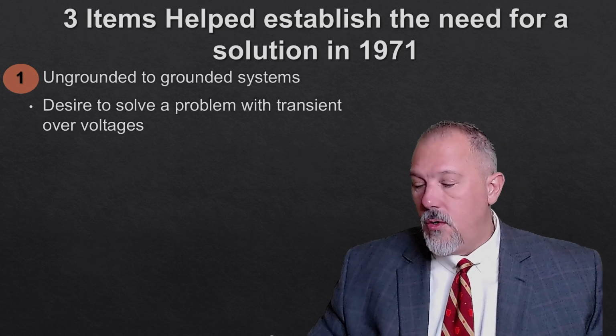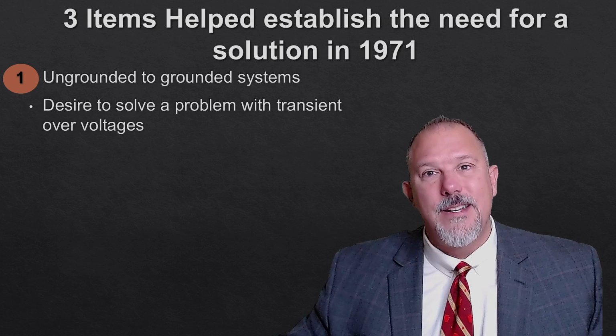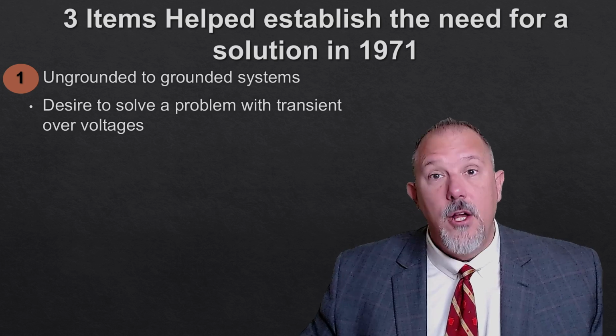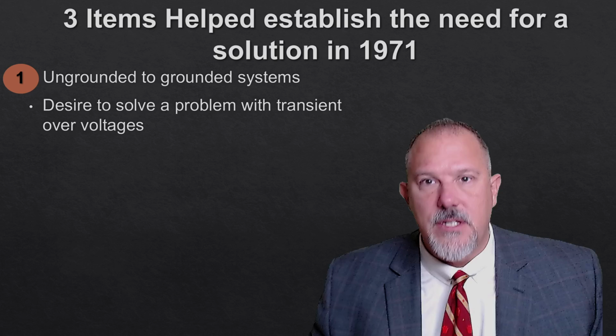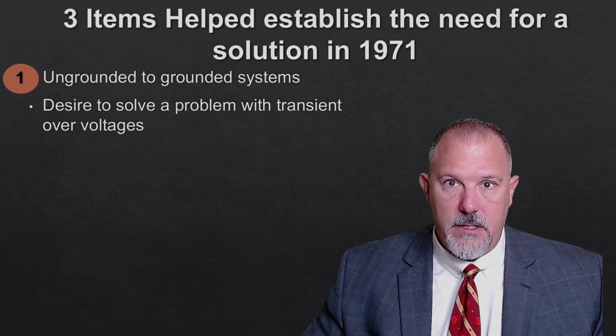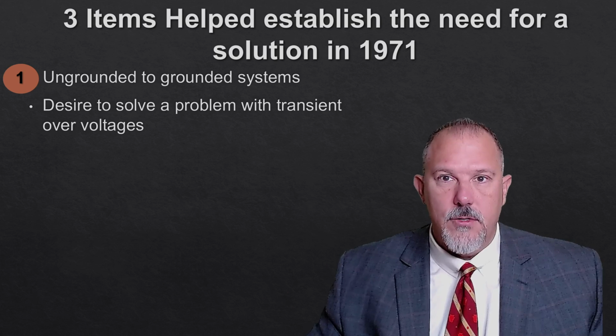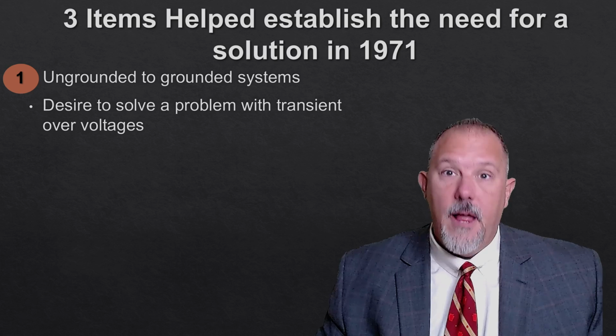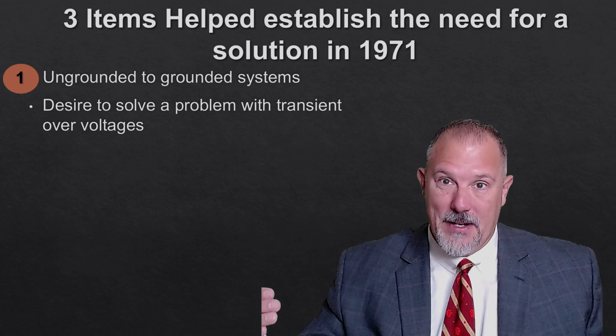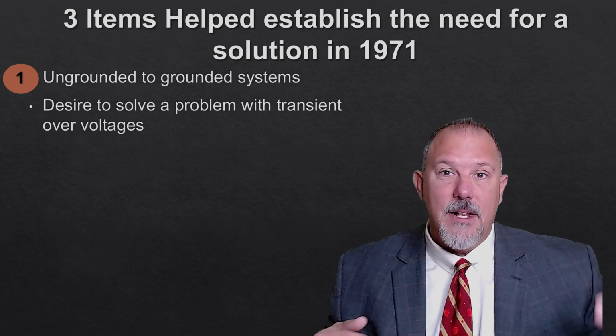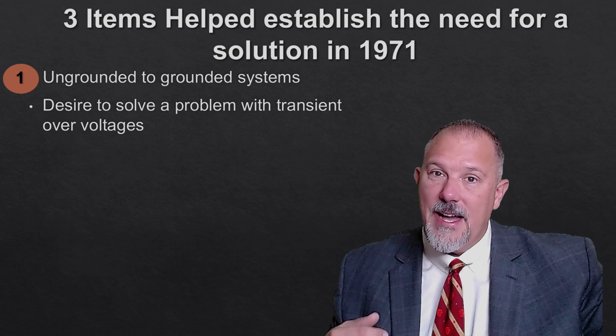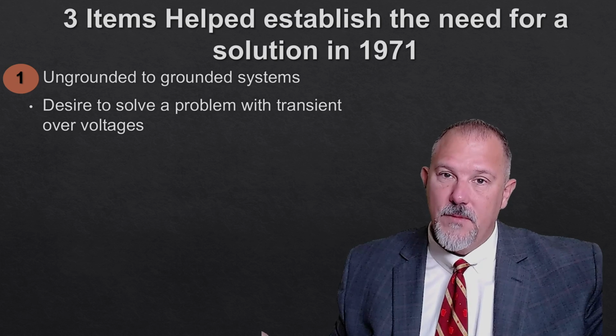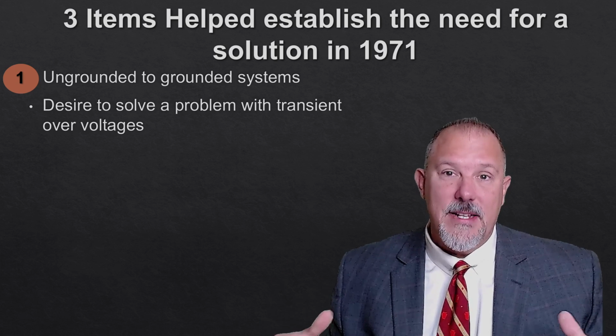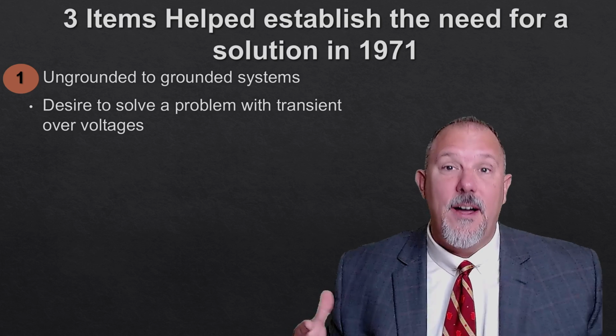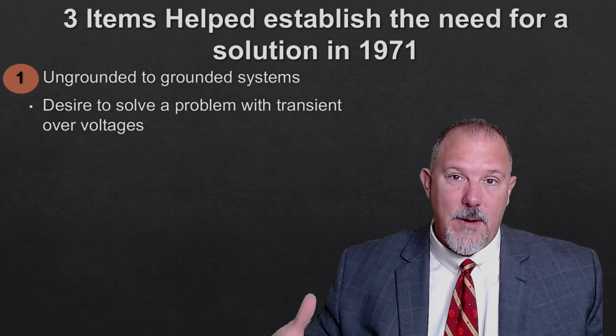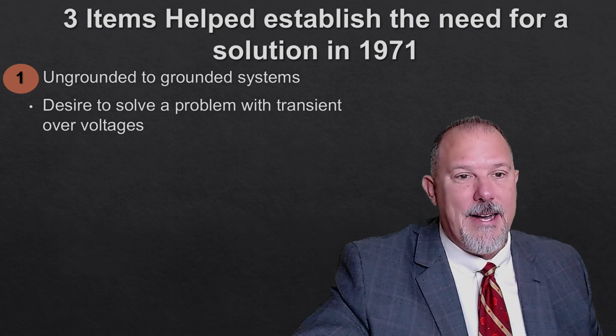So your goal as a facility engineer is to clear that fault, find out where it's at, what phase it is on, where it is in the facility, and get rid of it. Because the next fault, you're living on borrowed time. The likelihood and severity of that second fault: likelihood could be relatively high depending upon the first fault. But we know the severity of that second fault is tremendous because you have a grounded system. These fault currents are going to be high.